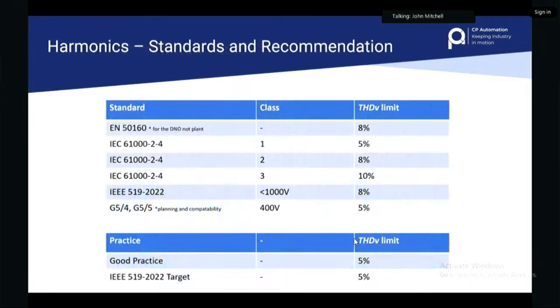This is just a list for some bedtime reading of some standards. Forgive me, I'm not 100% familiar with the standards adopted across the African nations. I know NRS 048, I think it is, in South Africa, but I don't know what's used further up north. So have a look at your local standards and see, but they probably conform to these, or you might even be using the American standard, which is kind of globalized, IEEE 519. But either way, 5% voltage distortion should be the ideal upper limit to make sure everything on site is good.